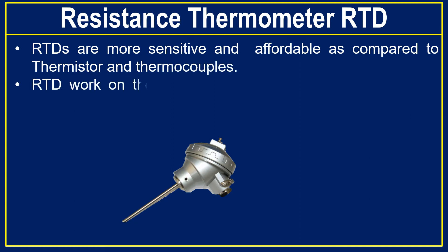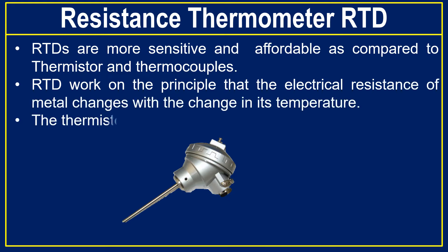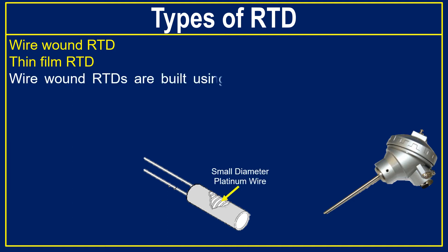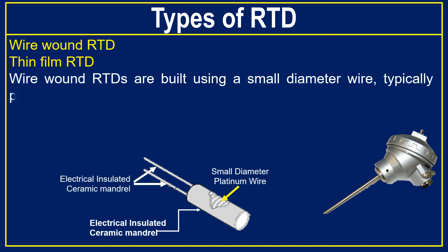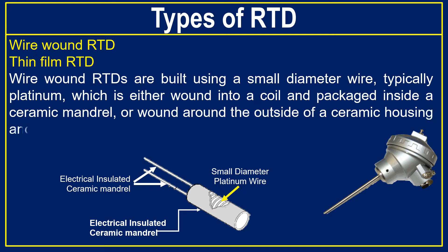RTDs work on the principle that the electrical resistance of a metal changes with the change in its temperature — the same principle as thermistors. There are two main types of RTD: wire wound RTD and thin film RTD. Wire wound RTDs are built using a small diameter wire, typically platinum, which is either wound onto a coil and packaged inside a ceramic mandrel, or wound around the outside of a ceramic housing and coated with an insulating material.